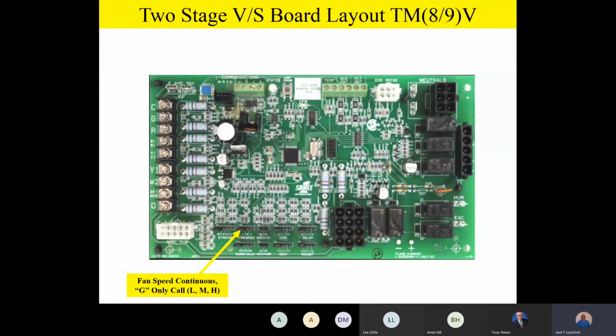Now, please make note of this. Low is about 35% of cooling airflow. Medium is about, and the reason I'm saying about is because on a couple of the products it changes a little bit, 50% cooling airflow. And high is 100% cooling airflow.